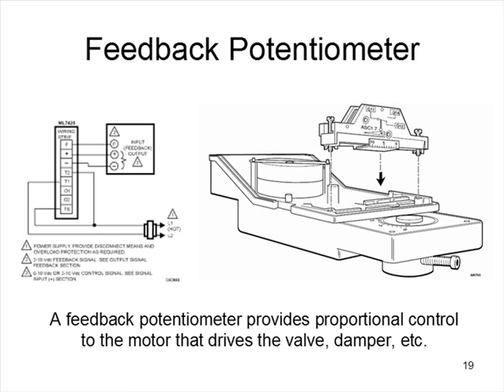It starts to allow a small amount of refrigerant into the evaporator relative to the load, because it won't take a lot of time. If it did open wide, it would shut down quickly, and that would create hunting. That's when a valve is oversized. Wide open, it floods the coil with cooling, and then boom, shuts down, right? But this feedback potentiometer works very much like a TXV valve does.